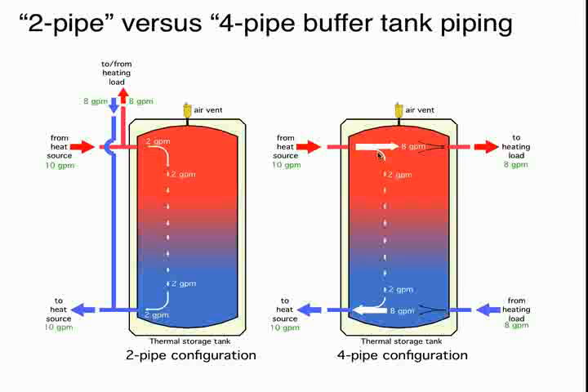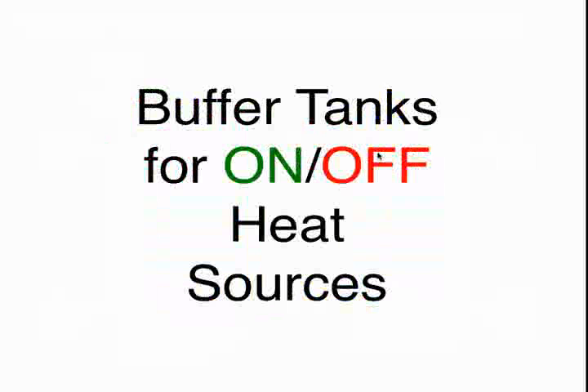We want to maintain stratification in the storage tank. It is more useful in a tank when that tank is properly stratified. So we want to get away from piping geometries that would cause any kind of, especially vertical flow velocities, excessive vertical flow velocities in a tank, because ultimately that will tend to stir the tank. And I'll show you some examples of some installations where that's occurred.